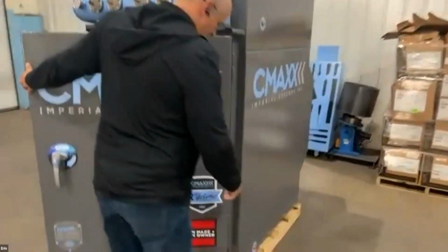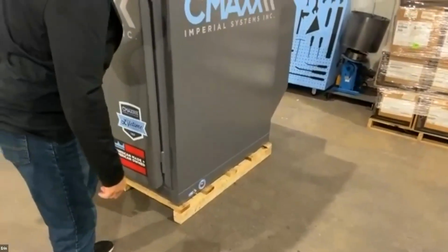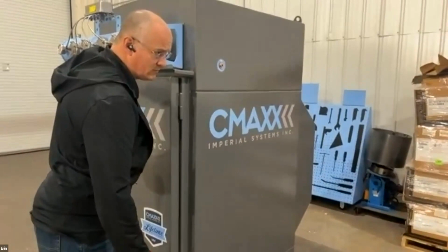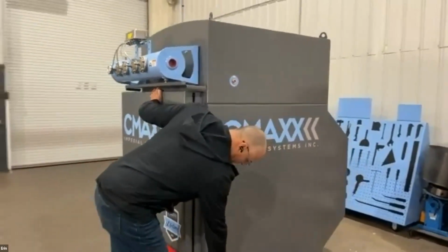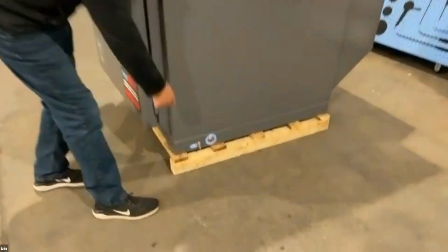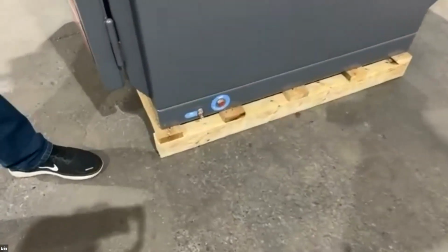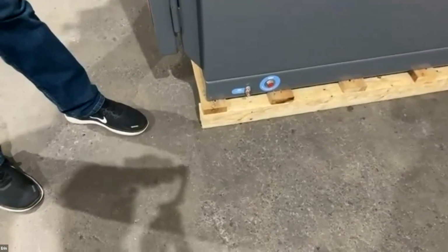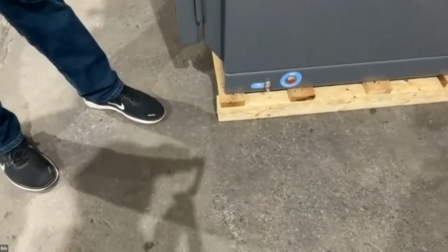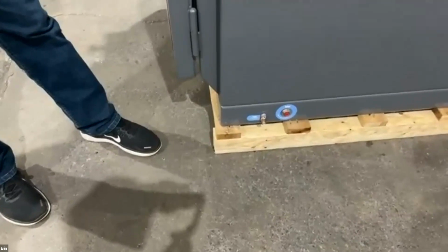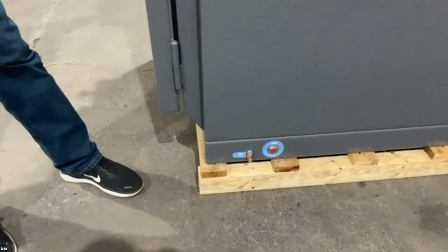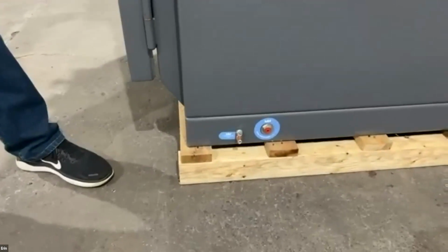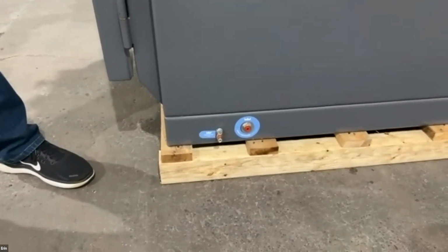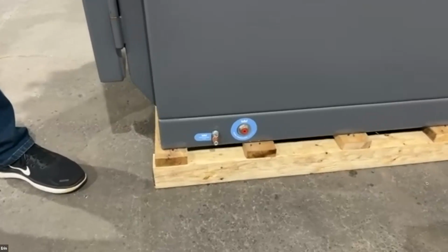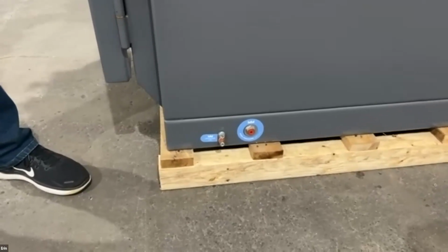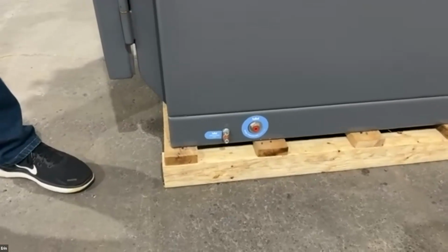Hey, Donovan, hold on one second before you go further. Different question, but this is a good point. I want you to keep going with this. The collector and the ductwork have to be grounded. We didn't really touch on that. There's static that will build up running through it. If you have a metal pipe system all the way through, as long as you don't have a section, some people will put a clear section of plexi or Lexan in there to see the actual dust coming through and make sure you're not getting any dropout. You have to ground across anything that isn't a continual ground all the way through your collector. And then the collector itself will have a grounding lug that the electrician must hook up to and actually sink a ground into the ground to actually ground it.